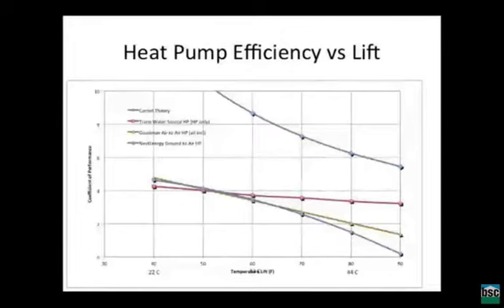So we ended on a chart that said when heat pumps try and lift temperature a lot, their efficiency goes down. And one of the things that Bruce Harley asked is, how can you get a COP of less than 1? How can you put in 1 watt of electricity and get less than 1 watt of heat out? Actually, it depends a bit on the system, but a lot of the systems have their compressor outdoors, the standard system. And as they try harder and harder to move heat, they get hotter and hotter. And they begin to lose heat to the outdoors.